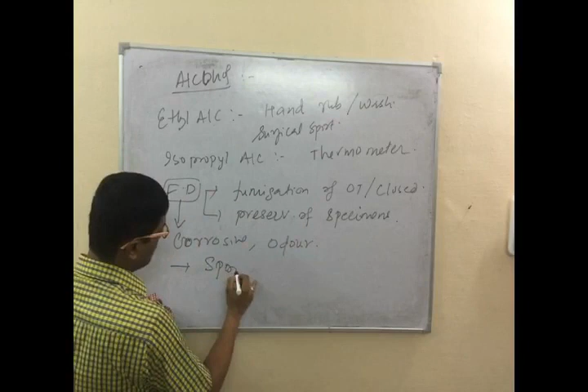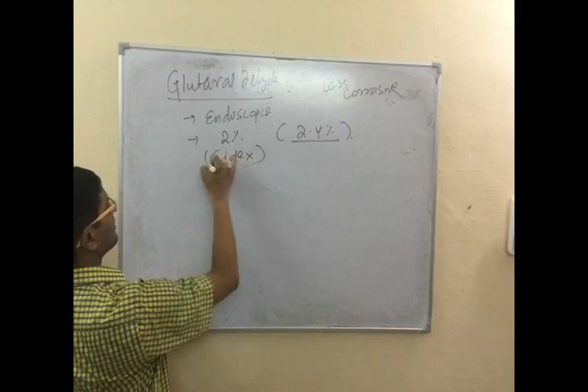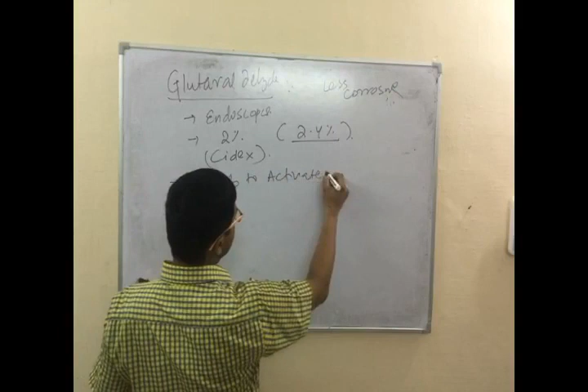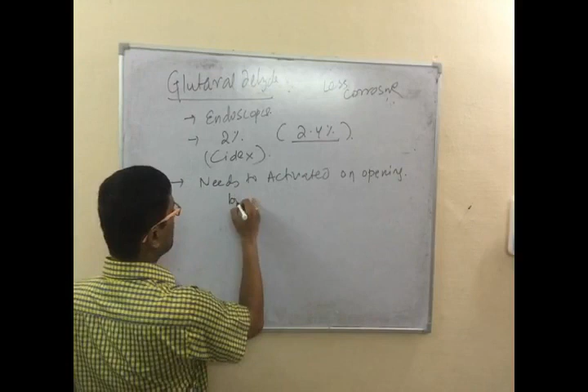Because it is corrosive to metal, formaldehyde is not recommended for sensitive metal instruments like endoscopes. For this purpose, the best method is glutaraldehyde. Glutaraldehyde is equally efficacious as formaldehyde, but it is less corrosive. Hence, it is best for endoscopes. The various endoscopes, cystoscopes, bronchoscopes, laryngoscopes, all these are better sterilized by glutaraldehyde. The usual concentration is 2%, but now CDC recommends using 2.4% glutaraldehyde. The most famous commercial brand is Cidex. Glutaraldehyde has a drawback that it needs to be activated on opening of the bottle. The first time you have to activate the glutaraldehyde by alkalization.